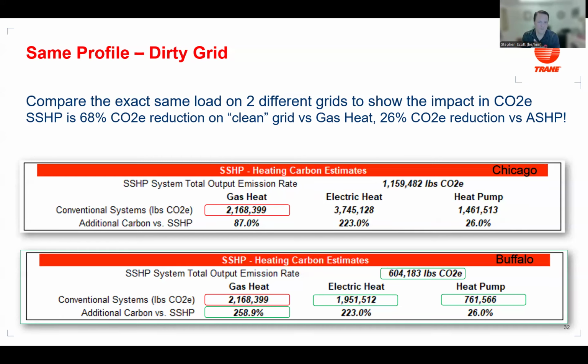When we convert that and look at the storage source heat pump, operating more efficiently with higher coefficients of performance by sourcing from the ice tanks, we then get that energy efficiency increase, or CO2 emissions decrease. Even on a dirty grid, it makes sense. And also on a relatively clean grid like Buffalo's, we certainly can reduce the CO2 equivalent emissions. Again, it all depends on what your targets are, whether it be your company's targets or your building's targets. If it is a CO2 emissions target, then this is just a different way of looking at it.